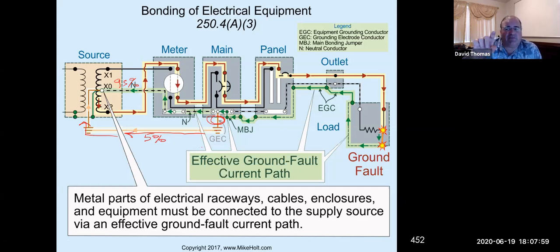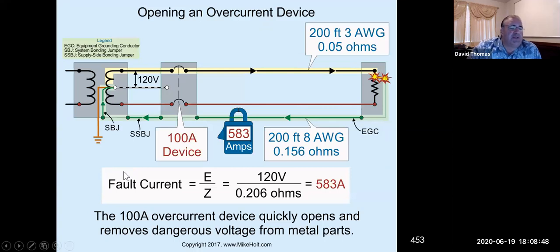The only problem is the socket itself is energized, so you can't stick your fingers in any of that area. They have plastic covers that fit on there in that case, if you ever have that condition. I've had to do that before when I'm servicing. I found the main breaker actually was bad, so I had to change the main breaker, and the easiest thing was to pull out the meter so I could isolate the main breaker. So just to make you aware of those things. If you shut the power off to the building, you shouldn't have any current flow on the grounding electrode conductor. You shouldn't have any current on there. Okay.